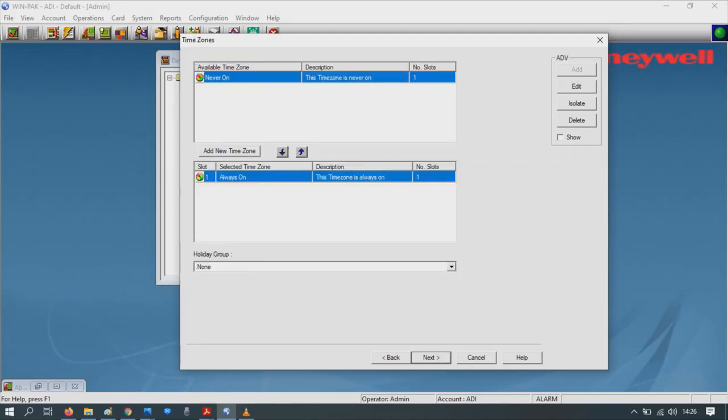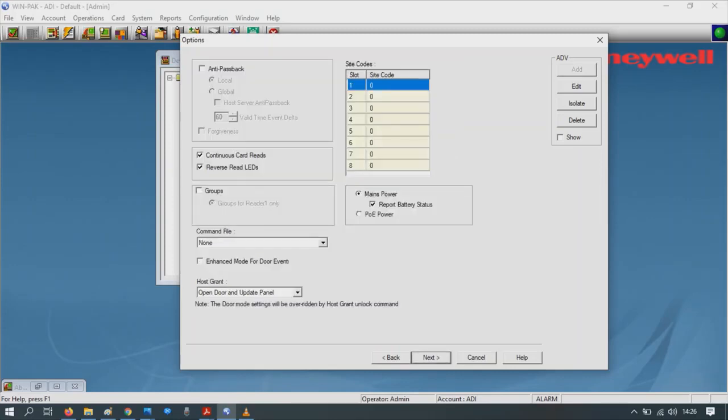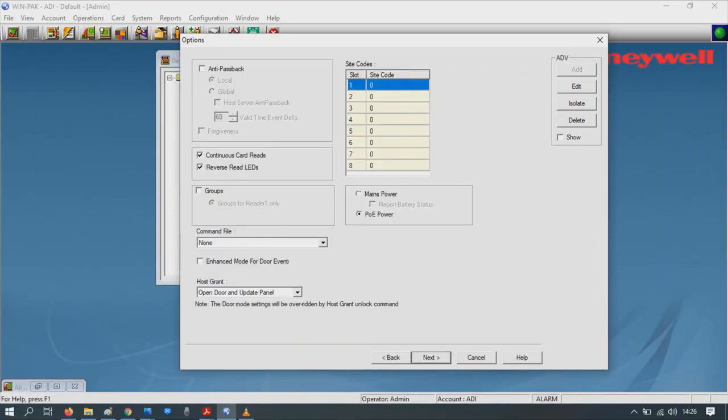Holidays: have we got all the holidays we want for this door? The answer is yes. Next, maybe add the site code if you like. In this instance we're powering this device on PoE, so select PoE power so you don't get battery warnings.